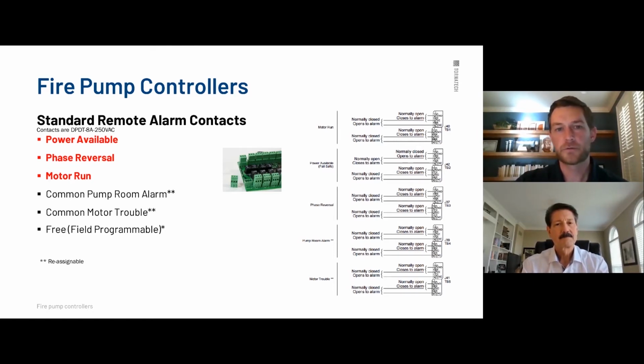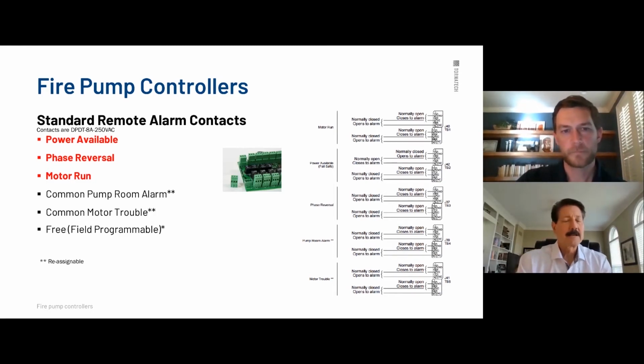It's free. You can do whatever you want to with it. You can adjust these other two as well, the common pump room and common motor. The three that are in red are the three that are required. You can't do anything with those. Those are hard set into the programming. But each one of these is double pole, double throw, meaning that you can send the signals to multiple remote alarm annunciators if that is a requirement. So these remote contacts, I'll add in here, Cole.